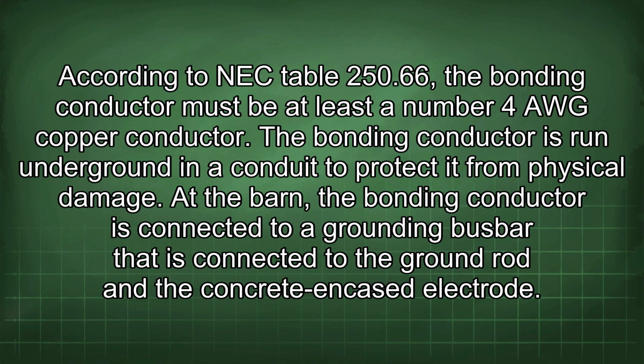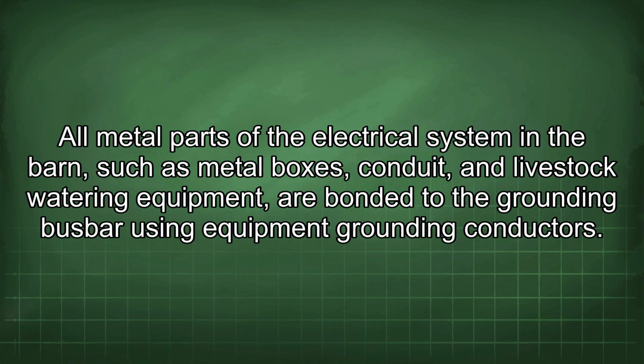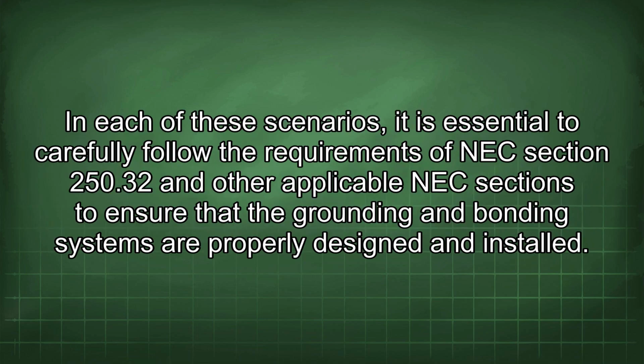At the barn, the bonding conductor is connected to a grounding busbar that is connected to the ground rod and the concrete encased electrode. All metal parts of the electrical system in the barn, such as metal boxes, conduit, and livestock watering equipment, are bonded to the grounding busbar using equipment grounding conductors. In each of these scenarios, it is essential to carefully follow the requirements of NEC Section 250.32 and other applicable NEC sections to ensure that the grounding and bonding systems are properly designed and installed.